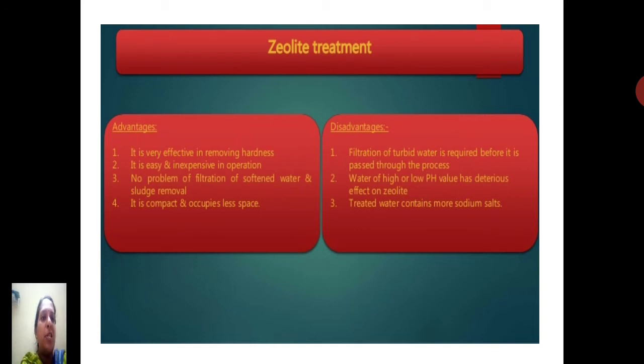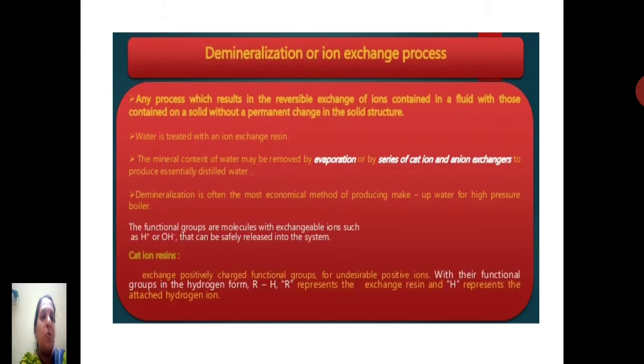When we come to the disadvantages, filtration of turbid water is required before it is passed through the process, and water of high or low pH value has a deleterious effect on zeolite. The treated water also contains more sodium salts.